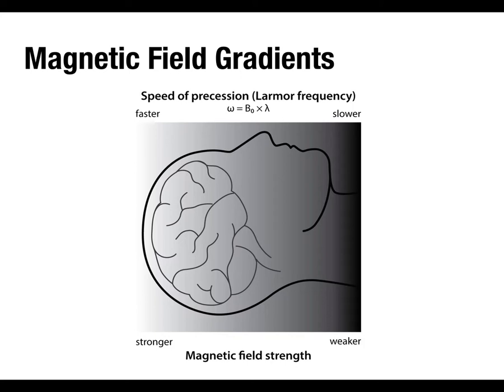The critical thing to produce a 2D or 3D image is creating a magnetic field gradient — which basically means a slope. In MRI, it's a gradient in the strength of the magnetic field. So in a 3 Tesla scanner, somebody's in there at 3 Tesla, but you can create additional magnetic fields using gradient coils — other components inside the MRI scanner. Those gradient coils allow creation of a variation in the strength of the magnetic field across any spatial dimension: X, Y, Z, or some angle between those.